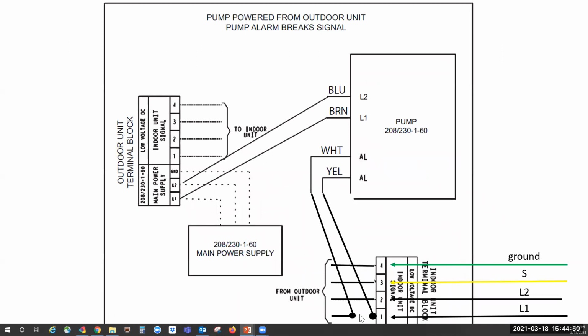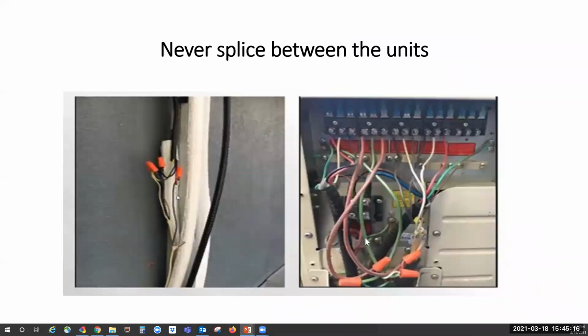Down here, we got this L1. That would be where you would break it in order to shut the unit down if the condensate pump failed. If you wire it in with L1, then you should not have any communication failures because this wire is still going to be solid, your signal wire, and your L2 will still be solid. You won't have any splices. And remember, never splice between the units. Splicing's bad.